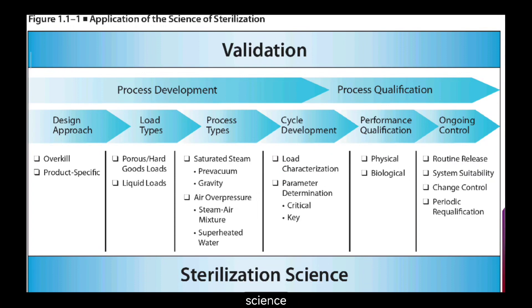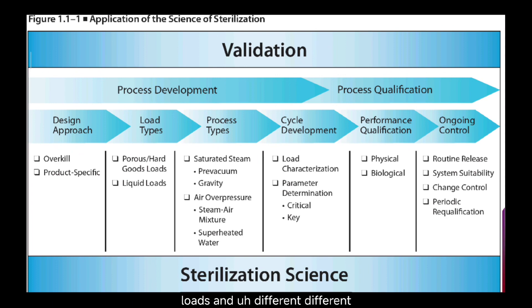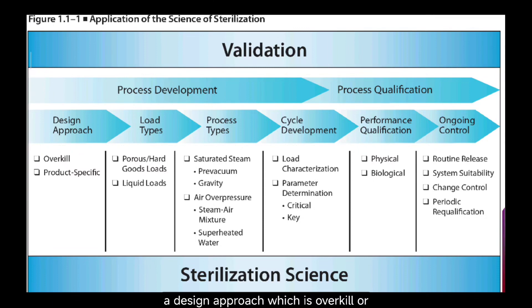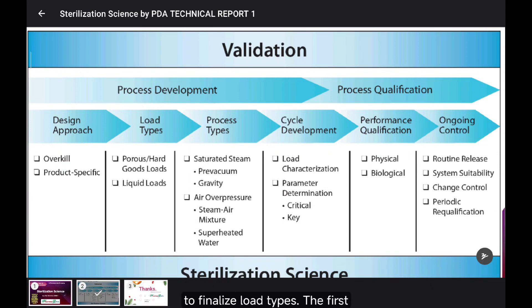Sterilization science generally has two phases: the first is process development and the second is process qualification. In process development, first we have to select a design approach — which design approach is applicable for sterilization of articles and loads. There are different types of loads, so first we need to select a design approach, which is either overkill or product-specific design approach.